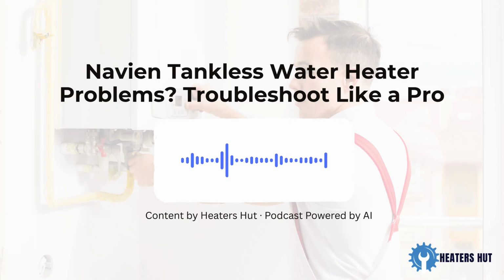It sounds almost too simple. What's actually going on there that makes it work sometimes? Yeah, it's fascinating how often that little action does the trick. See, that valve is there to vent excess pressure. But sometimes maybe a tiny air bubble gets trapped, or the pressure just gets a bit uneven in the system. Opening and closing it quickly helps release that trapped air or just balances out the pressure. That can reset things, essentially telling the heater's sensors, hey, water's flowing. Once the pressure's right, the flow sensor gets a clear signal and boom, hot water again.